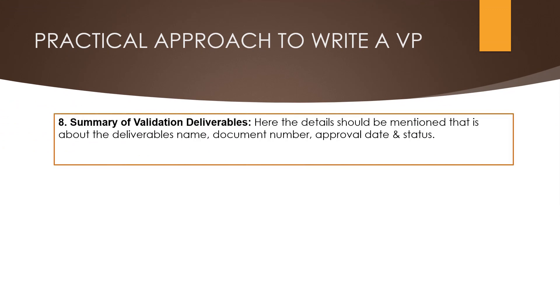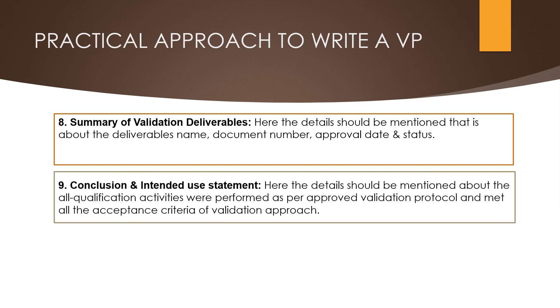The eighth component is the summary of validation deliverables. Here details should be mentioned about all deliverables — name, document number, and approval date. The ninth component is the conclusion and intended use statement. Here the details should mention that all qualification activities were performed as per the approved validation protocol and met all acceptance criteria of the validation approach.